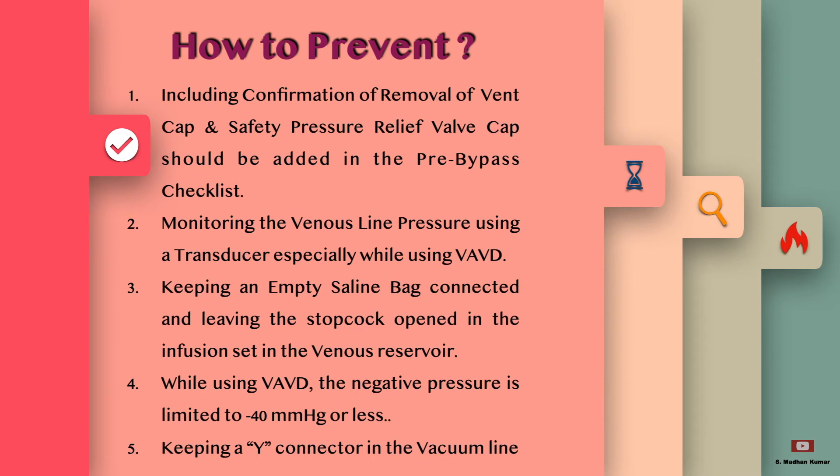Always keep a Y-connector in the vacuum line with a safety clamp present on it. If positive pressure develops inside the venous reservoir, we can always release the pressure immediately by unclamping the safety clamp.